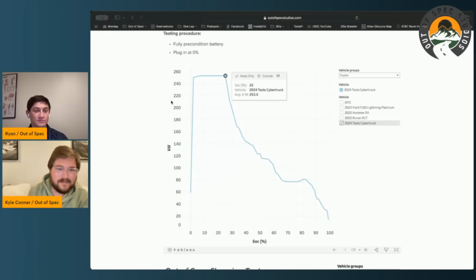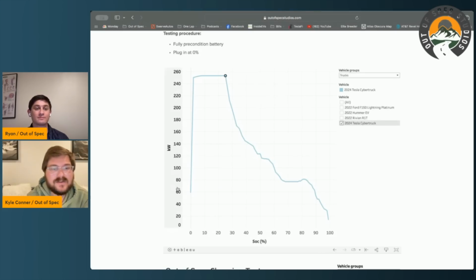You want those 1% arrivals, 0% arrivals. If you're going to run it down to 0, watch the power meter on the screen. If you really get a lot of dots coming in, keep in mind BMS miscalibration may happen, they may not always have a buffer below 0. So just watch the power limit, that's a good way to avoid getting a confused BMS.